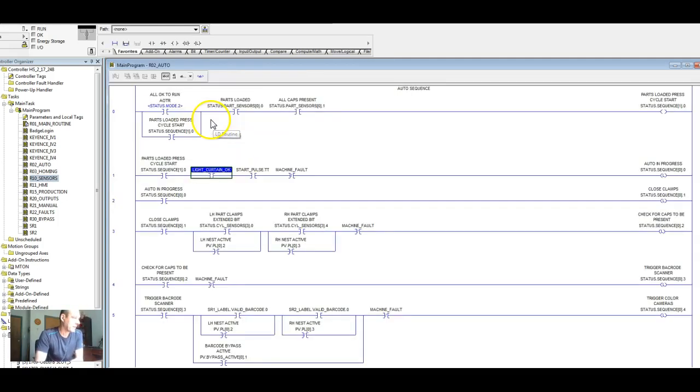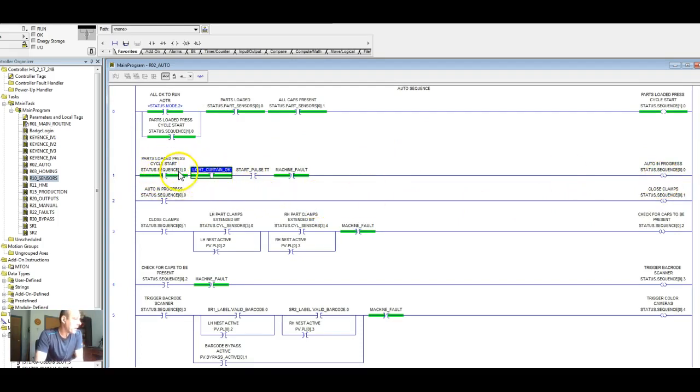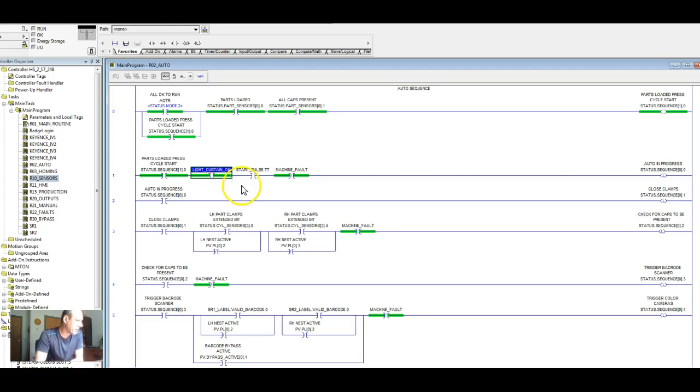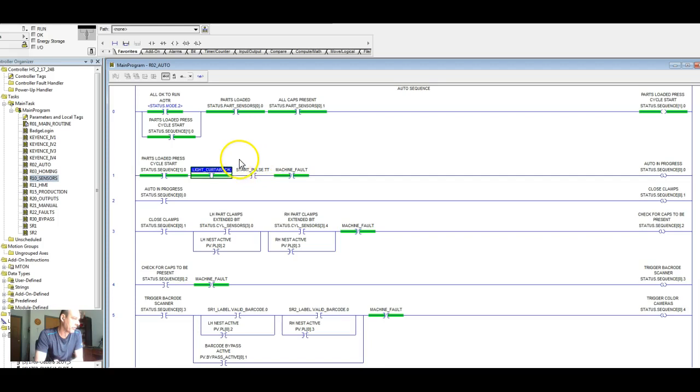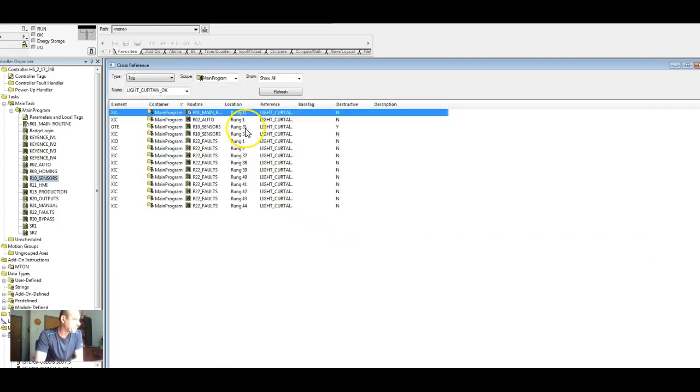So let's go back and let's cross-reference again. So in our auto cycle, auto in progress, if the parts aren't loaded, cycle start, the light curtain's not okay, we don't get our start pulse or there is a machine fault, we can't go into an auto cycle. Very simple.